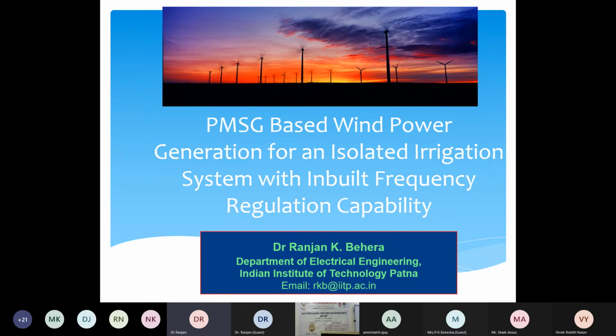Whereas when you are connected to a system which is a 50 Hertz system, but starting a big inertia motor machine generator, the generator will slowly start building the frequency from 0 to 50 Hertz. This building time, in case of a grid integrated system, needs a lot of attention, or it may damage the complete unit or destabilize it.